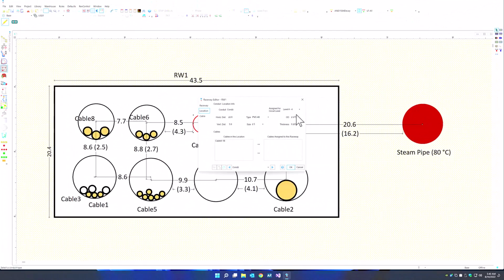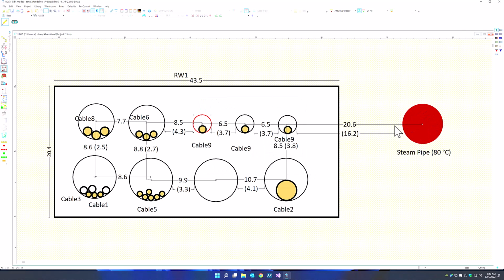In the ETAP underground raceway system, you can see the new conduit types in our drop-down list for the conduit type selection. And you can also see the new annotations available to us, for example, the steam pipe, giving us the temperature of 80 degrees Celsius. And of course, you can also see the annotations for the center to center spacing as well as the edge to edge spacing that's available for the underground raceway system.